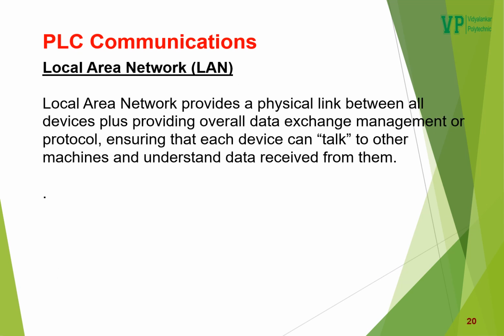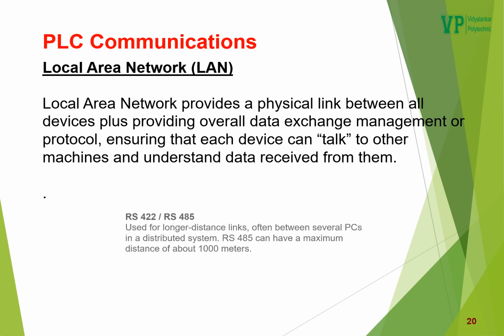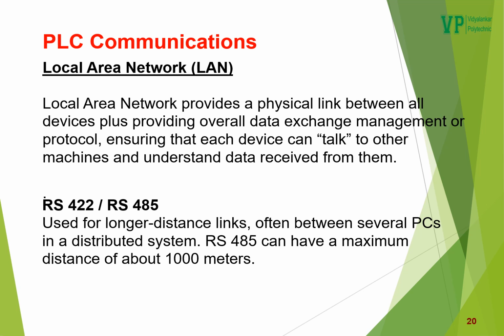Communication can also be established with the PLC through a LAN network. That is, if at all it is required to update the program in PLC, a LAN technology can also be used. LAN, that is local area network, provides a physical link between all devices, plus providing overall data exchange management or protocol, ensuring that each device can talk to other machines and understand data received from them. If at all the distance between the PCs and the PLCs is larger, then a different standard, that is RS422 or RS485, is implemented. Well, RS422 or RS485 can be effectively used for a distance as high as 1000 meters.